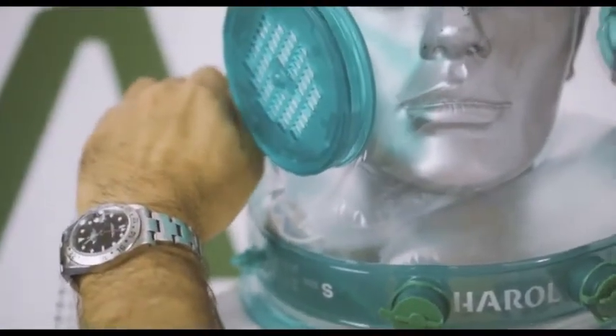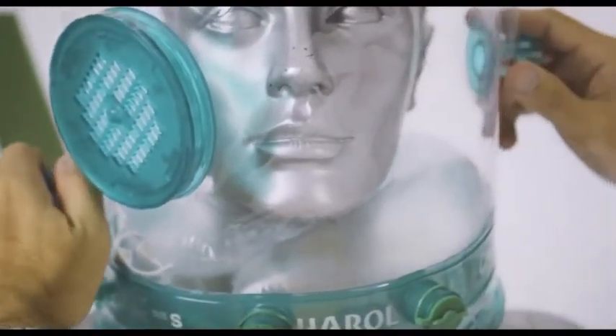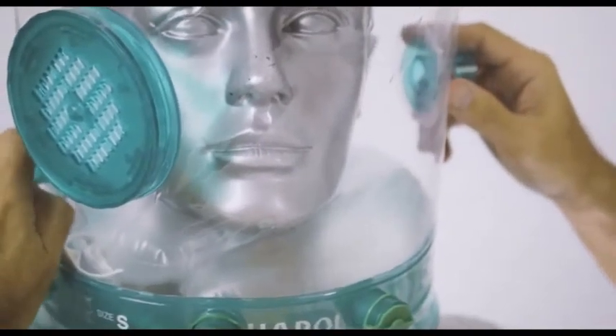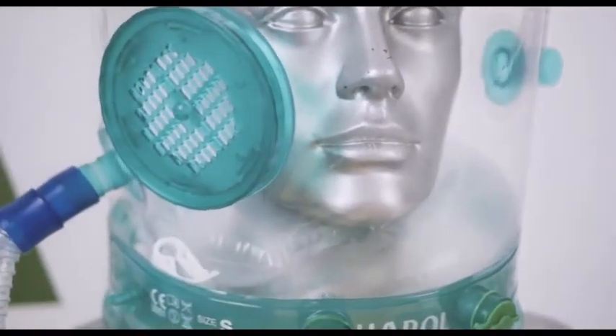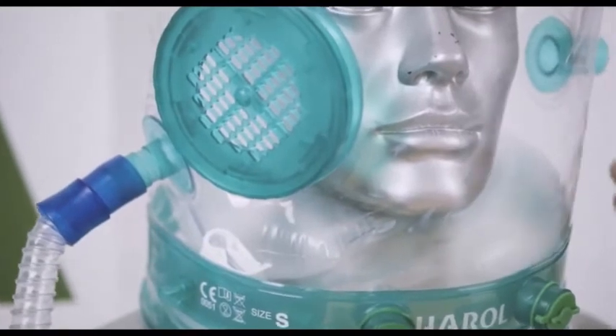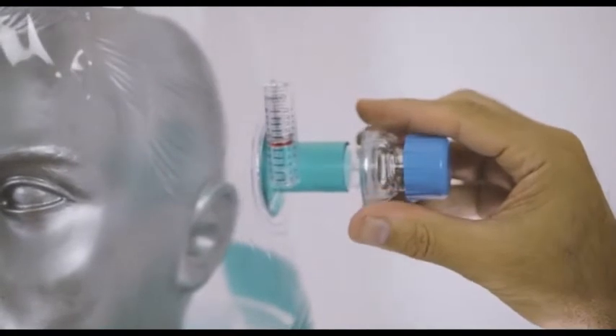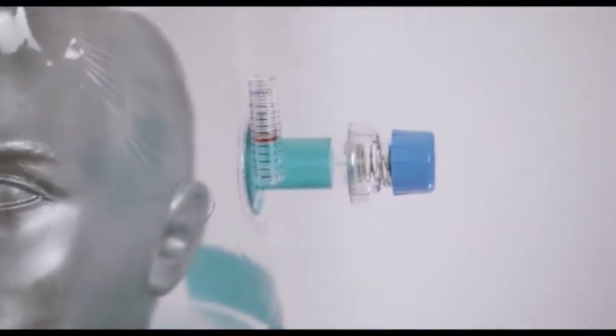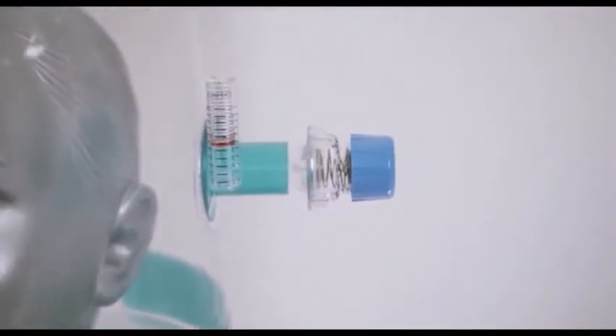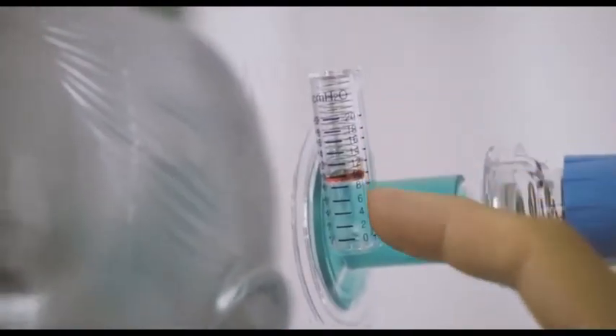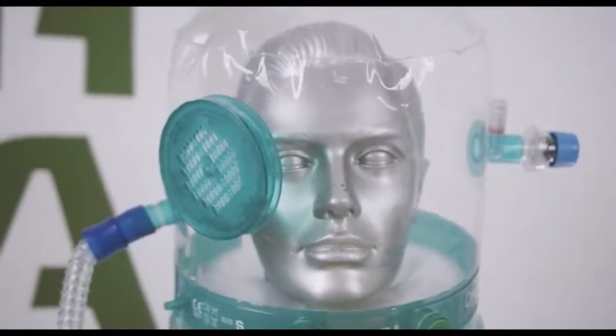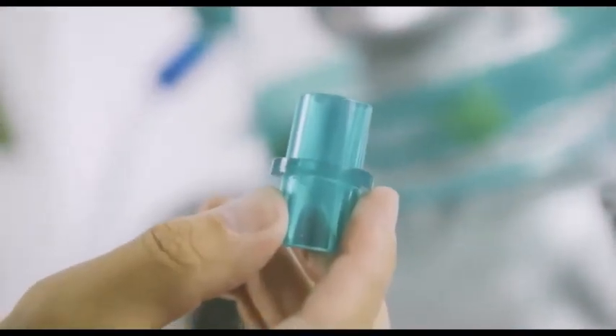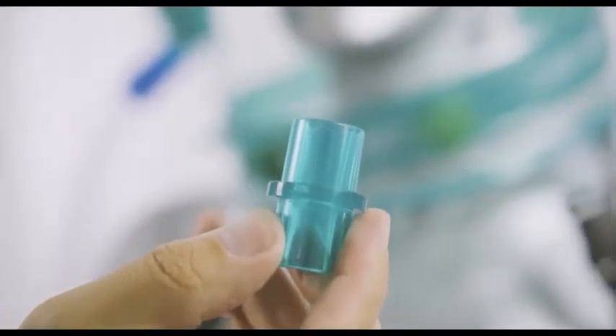On the sides of the tent, there are two connections. A 22mm male inlet, conforming to ISO standards, used for connecting the tube that will provide the flow, and a 22mm female outlet, also conforming to ISO standards, on which the PEEP valve will be connected. Next to the outlet connection, you will find an integrated manometer for PEEP measurement.